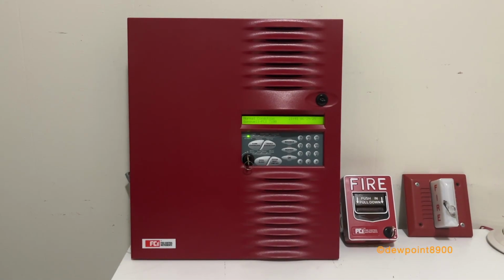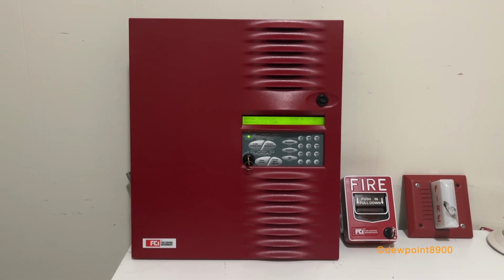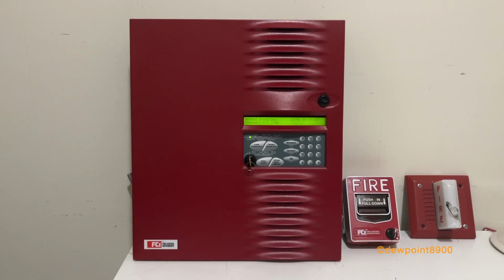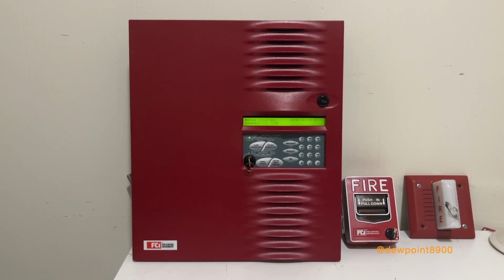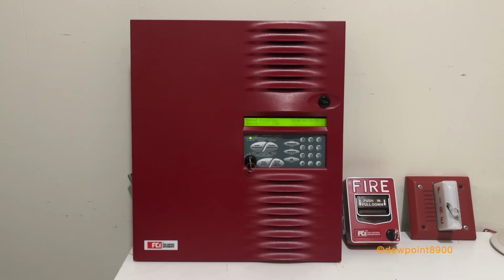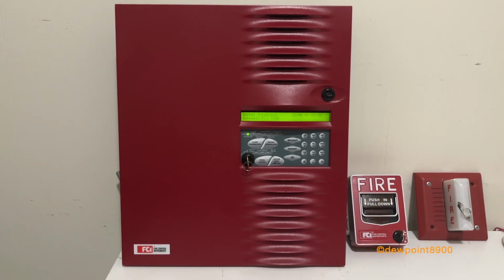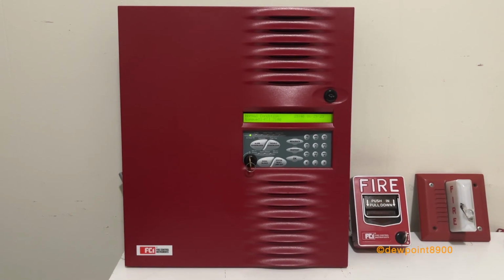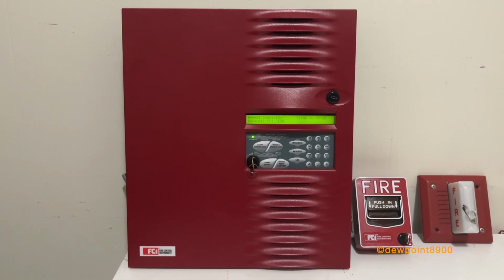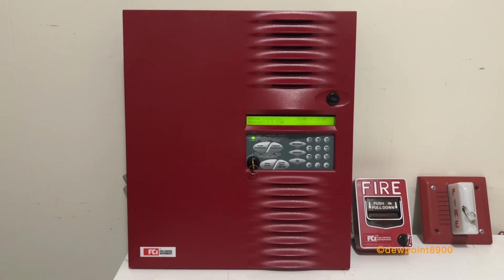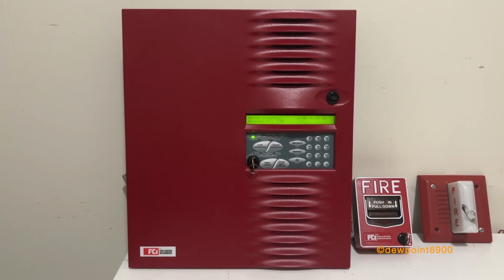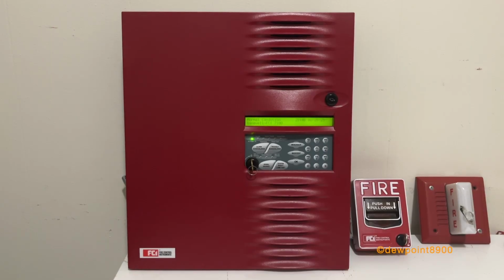Hello everyone, this is an FCI 7100 fire alarm control panel. These were first produced in the late 1990s and were designed for small to medium-sized facilities. The 7100 is a compact, cost-effective addressable panel with one or two SLC loops. Each loop can hold up to 197 devices, 99 detectors, and 98 modules.